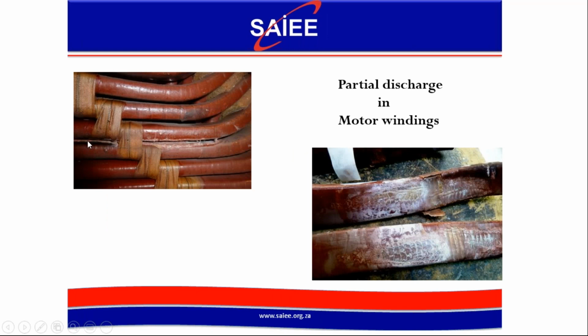Partial discharge comes into good winding practice as well. I know Rob in his session will be covering partial discharges, which is related to the spacing of the winding and the overhang. It's a slow process, but partial discharges do eat away the insulation. As you can see, that section there and the section here where we opened that and saw how the insulation had been eaten away, we would expect premature failure at that particular spot on the winding.